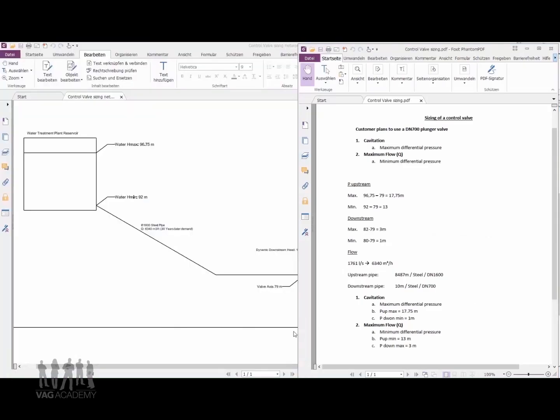When we size the control valve, there are two things that we are looking at. First and most important is to prevent cavitation, and this is when we look at maximum differential pressures. Secondly, the valve that we calculate in point number one also needs to be able to achieve maximum flow condition at the minimum differential pressure.